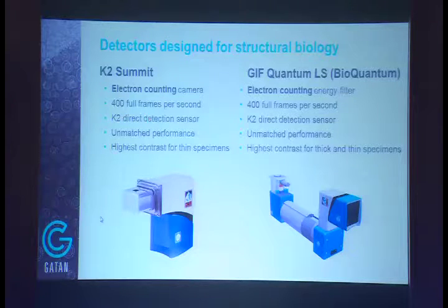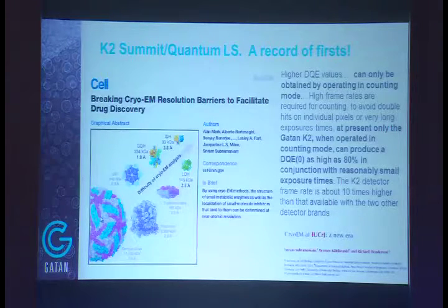And the K2 Summit is really great for high contrast on single particle work, relatively thin specimens. And for high contrast with thicker specimens, that's when you really want to be using an energy filter type camera. Okay. So the progress in this field has been really tremendous.